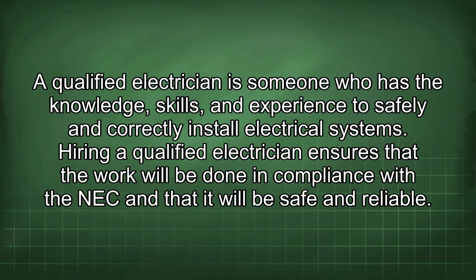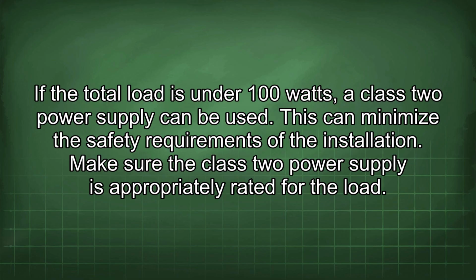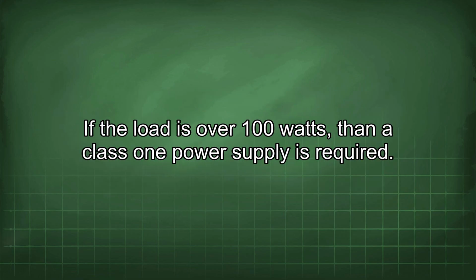If the total load is under 100 watts, a Class 2 power supply can be used. This can minimize the safety requirements of the installation. Make sure the Class 2 power supply is appropriately rated for the load. If the load is over 100 watts, then a Class 1 power supply is required.